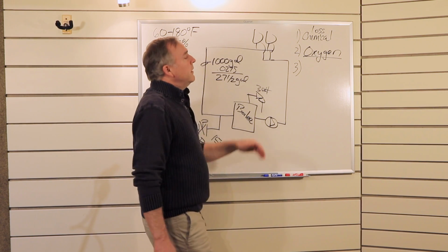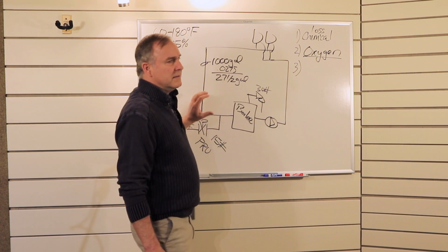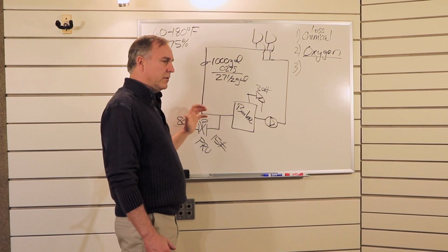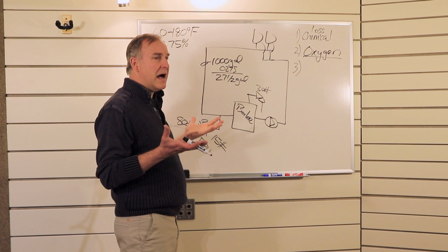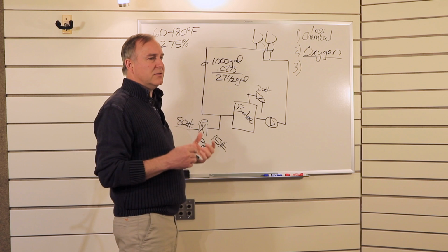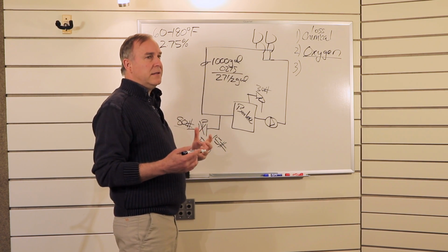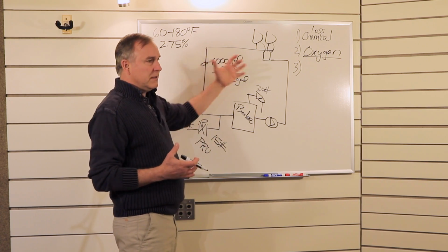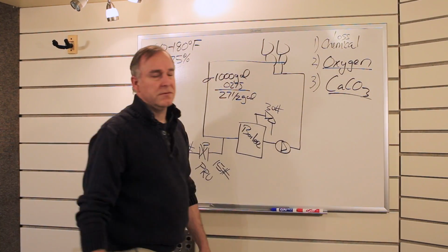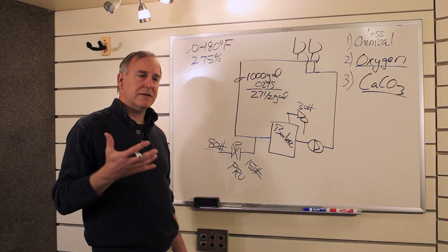The third is sort of an interesting substance that happens to be dissolved in our fresh water. And it has an unusual characteristic in that it becomes less soluble in water as we get hotter. That's very unusual. Most substances don't react like that. If you think about trying to stir sugar into iced tea, it's pretty hard. Stirring sugar into hot tea, pretty easy. But this particular substance, known as calcium carbonate, sometimes referred to as lime or scale, this doggone stuff becomes less soluble as the water gets hotter.